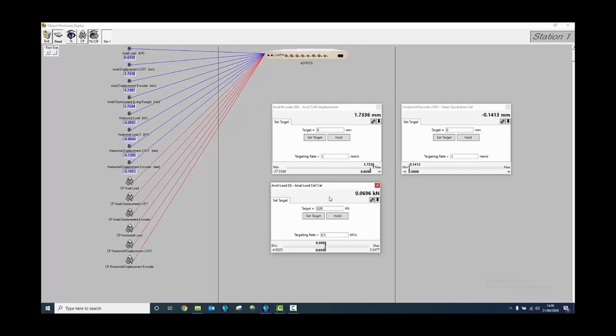Fast, and now that we have dropped the load, we can target a position that is above the sample, so you can safely remove the membrane and remove the pedestal. So I'll send the target to -1 millimeter. As you can see, our axial displacement LVDT went out of range because we moved above the sample. However, at this point, it doesn't matter because we'll be removing the sample from the assembly. So now we can have a look at doing that.